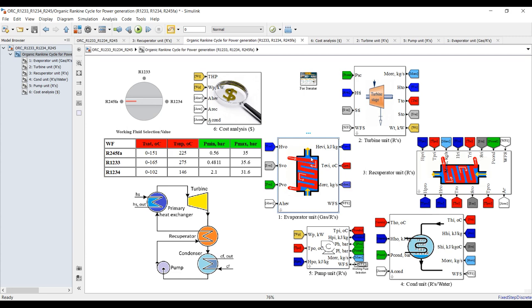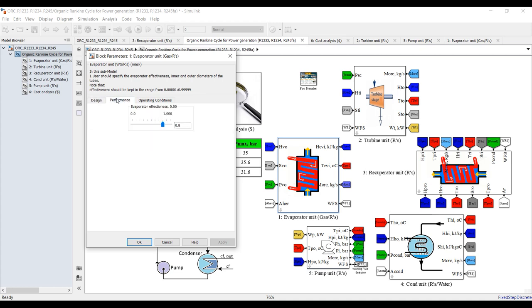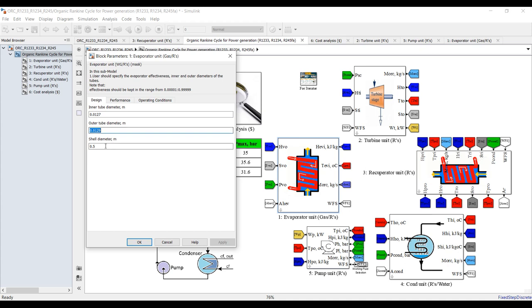Let's begin from the evaporator — just double-click. You have to assign inputs such as design, performance, and operating conditions. For performance, this is the effectiveness of your evaporator in design mode — we are calculating area and flow rate. Assign effectiveness, normally around 0.75 to 0.8 for heat exchangers. For design parameters, assign tube and shell diameter based on your design and examine your results.